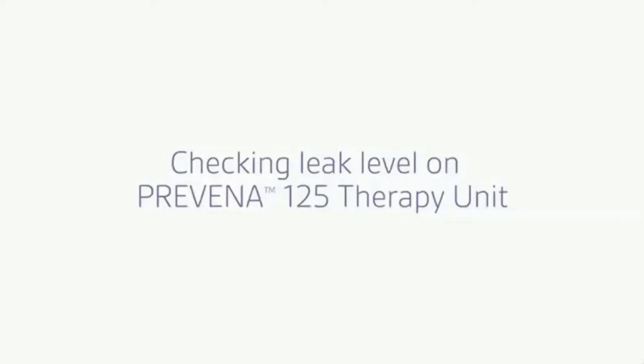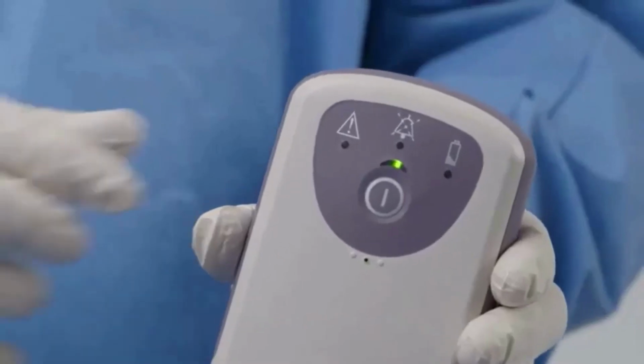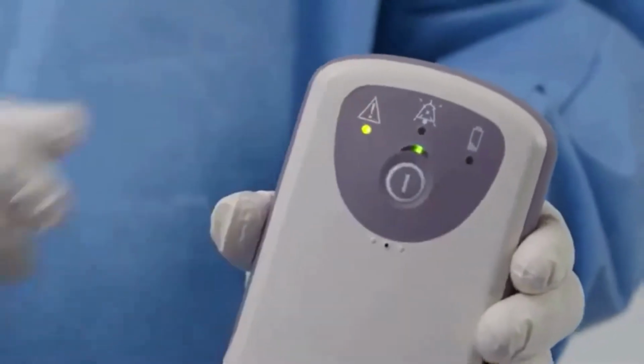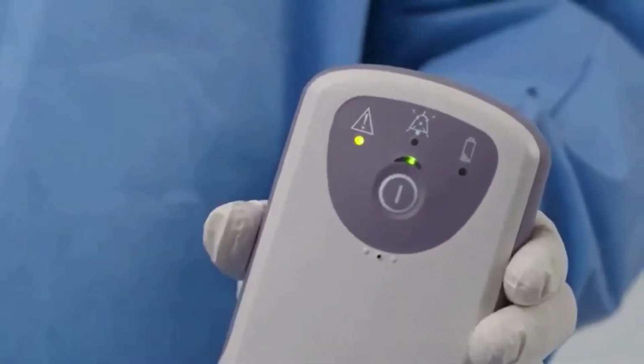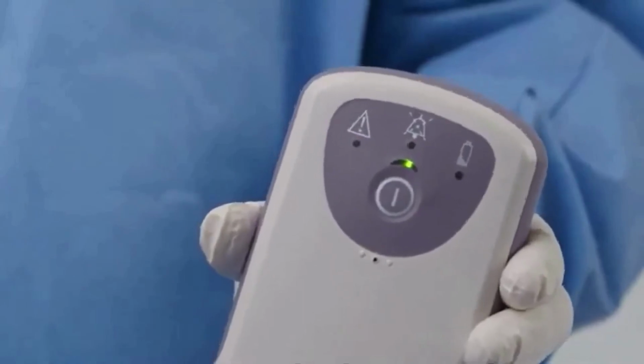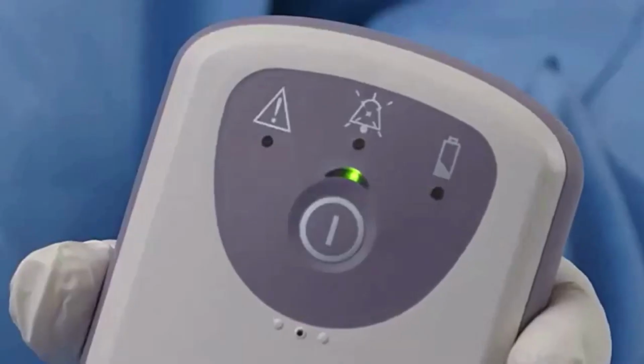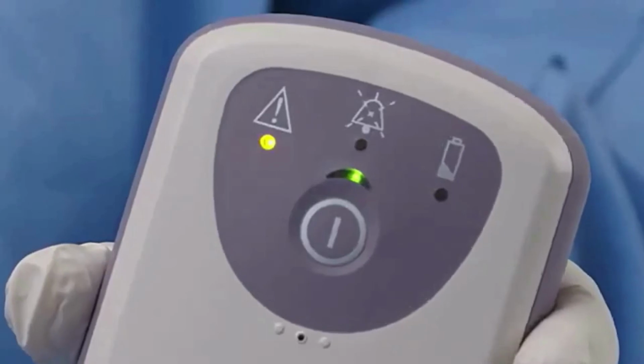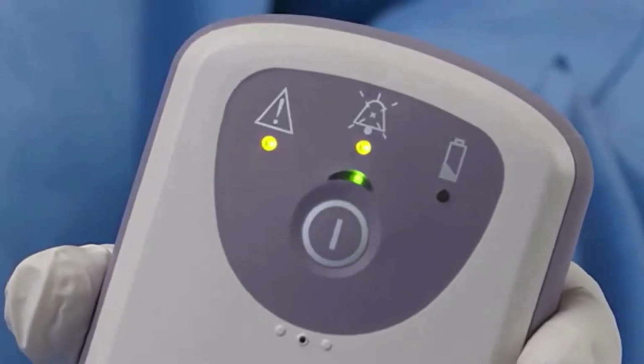The Prevena 125 therapy unit includes VisiCheck feature, designed to visibly indicate leak level. After the dressing is drawn down, double press the on-off button quickly. The unit will display the leak rate of the system for 3 seconds. The leak rate status should read best, 1 light illuminated, or good, 2 lights illuminated.